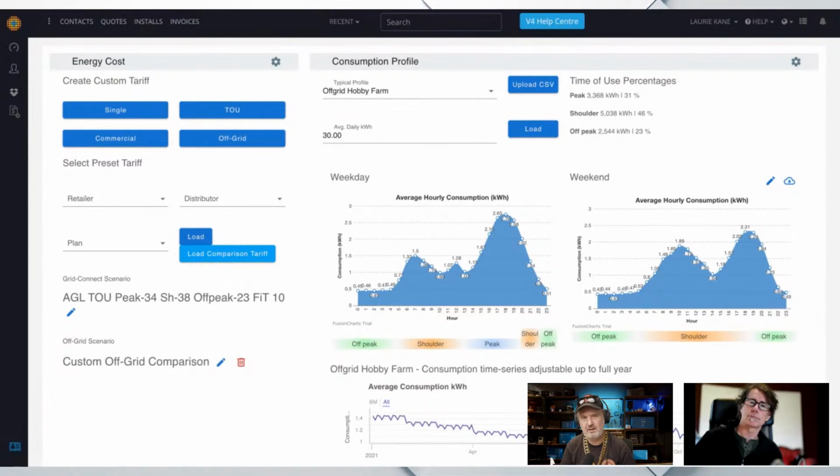Yeah, I often say that you should clarify with the customer what the surge demand limits are for the system. Like if they say, I want to be able to turn everything on and not worry, well, you just say, more dollars, please, because you put a bigger inverter in. But it doesn't really make that much sense because it's almost impossible to turn everything on. So, identify what the coincidental maximum demand is, things that are likely to come on together, such as water pumps and devices that use water, like washing machines. So, being more economical in your specification, that's a little bit outside of what we're talking about here, which is sizing solar and batteries. That's actually thinking about how the customer operates their system.